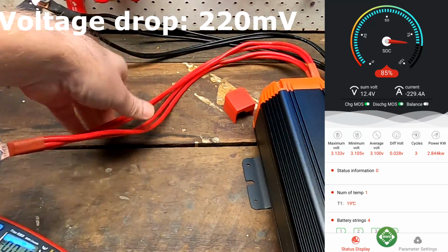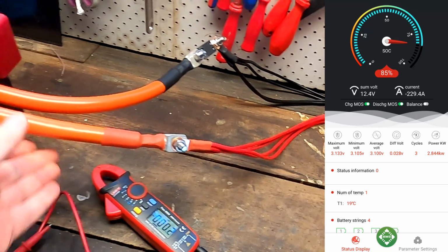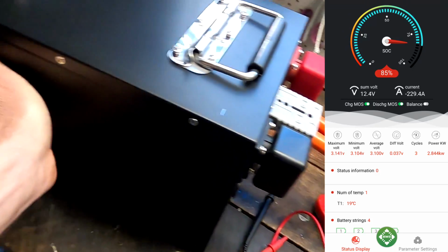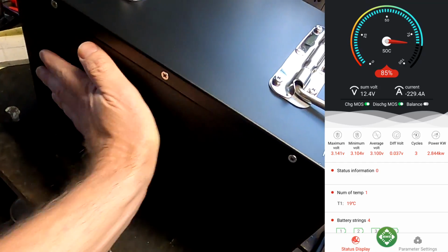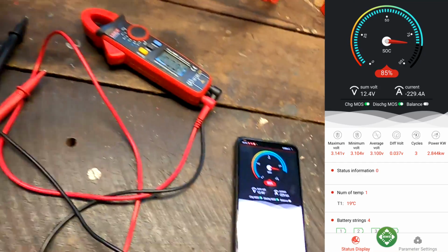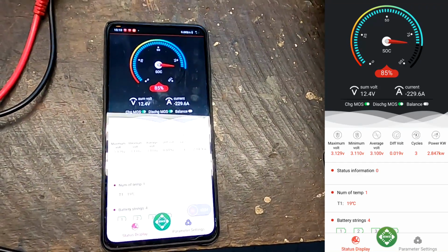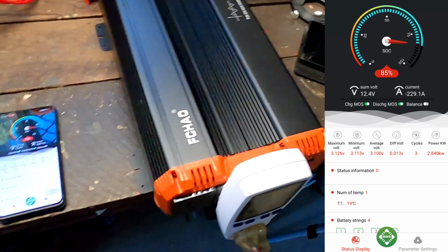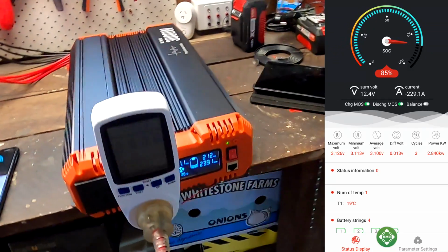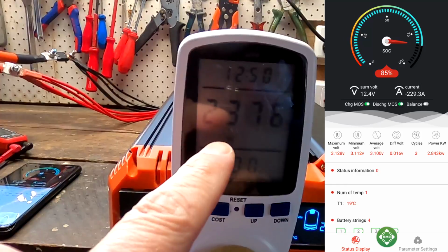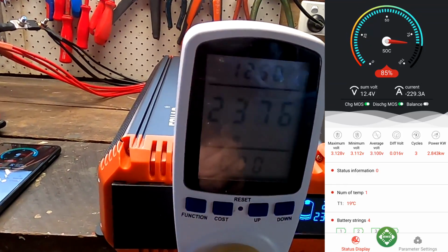110 millivolts we lose, times 2 just for the cables. So this is now with 230 amps discharge current, and we are going into a limit of this battery as well. The Daly BMS is rated for 250, so we are discharging the battery with 2.8 kilowatts, and 2.4 are going into the vehicle at the moment.